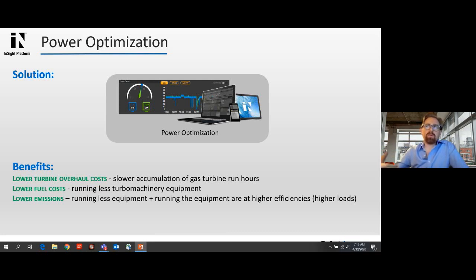Your fuel costs are obviously less if you have fewer units in operation, and your emissions profile is significantly less as well. You're running less equipment, and the equipment you are running operates at higher efficiencies. The gas turbine is much more efficient at higher load than at low loads.